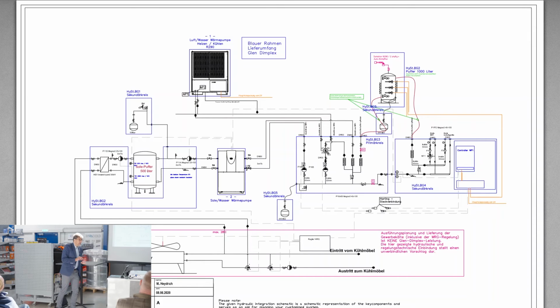And the important message is that it doesn't matter what circuit we have. It can be a liquid circuit, a water loop. It can also be a CO2 system on the heat source side. The functionality and the idea are pretty much the same. The controlling system is also provided by us, and it is quite different from the traditional one, because we are keeping the temperatures on this side. So we are taking care of correct temperatures in this loop. This is the main task to fulfill. The rest is the result.